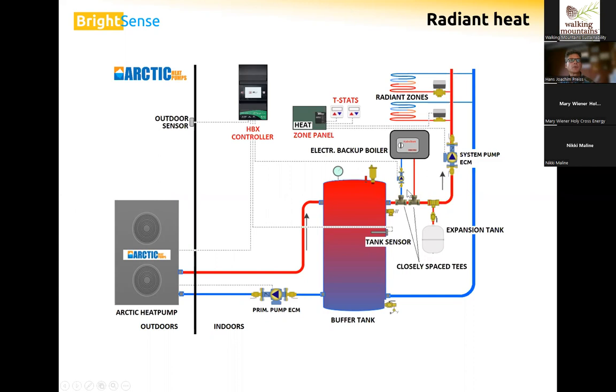But it's also a hydraulic separator. The boiler folks among you, they will know what a hydraulic separator is. The heat pump wants to see a constant flow rate here. Where on our radiant side, we could have one radiant zone calling or five or seven. So the flow rate on the radiant side can vary greatly. And that's why we want to have this separation between those two so they don't affect each other.